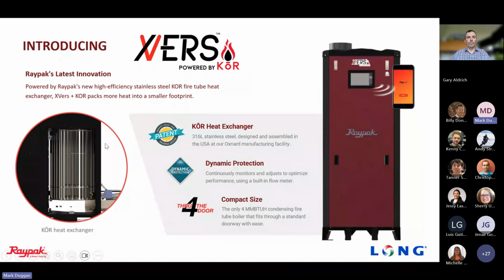For those of you that are not familiar with what a fire tube heat exchanger looks like, here on the left-hand side, you can see basically it is a stainless steel tank with all these little stainless steel tubes running across it. There's probably at least 100 tubes in there. And there's a burner that sits on the top here, and that burner is distributing heat through those tubes as the water circulates around it. So the water comes in through the bottom, circulates around those tubes as it heats up, and makes its way out of the top. So that's just a little icon of what a fire tube heat exchanger looks like.